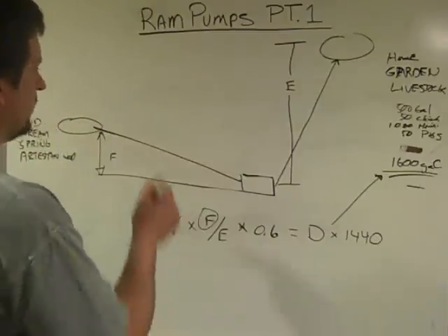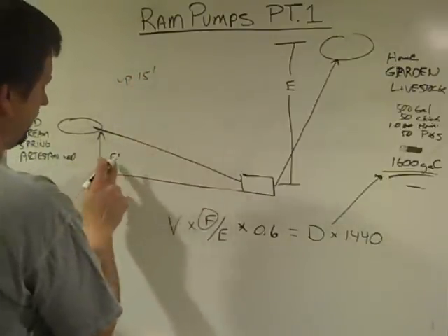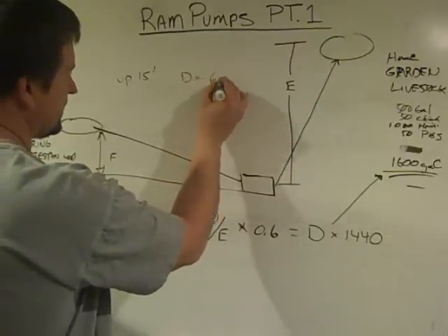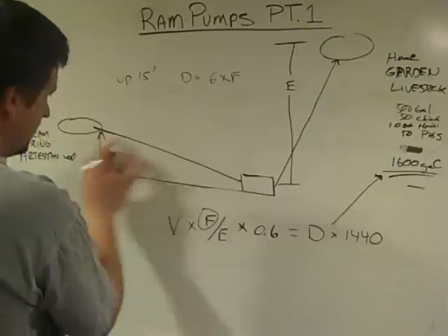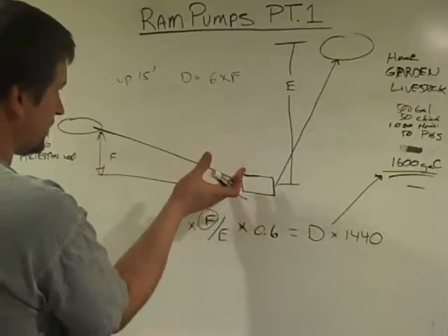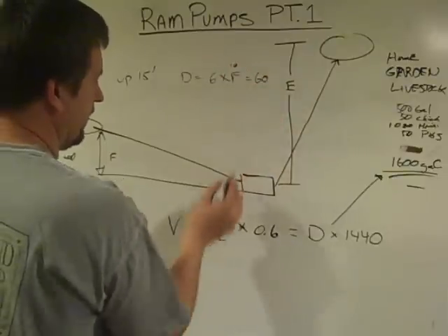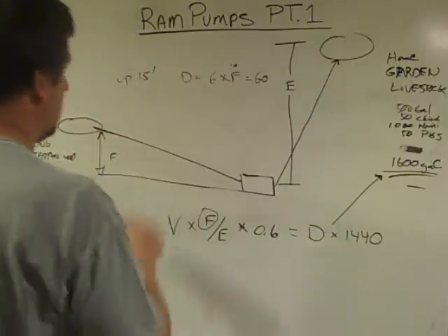Let me tell you some rules of thumb. If you go up to 15 foot of fall, your drive pipe needs to be six times whatever that fall is. So if your pump is 10 foot below your source, then if this was 10, then you would have 60 foot of drive pipe. Yes, 60 foot. Drive pipes are typically long.